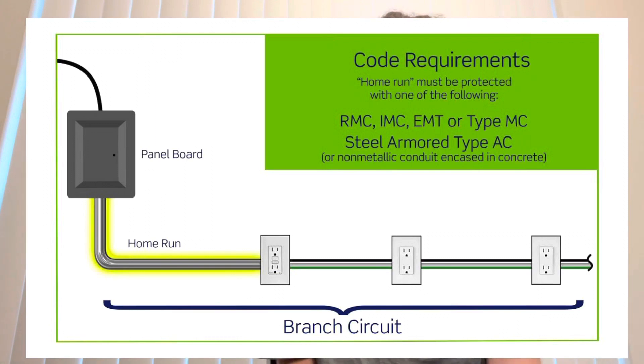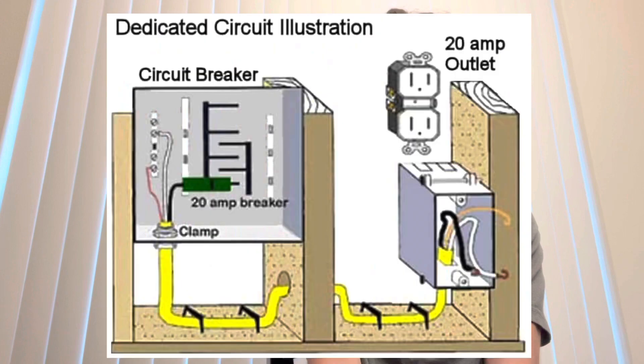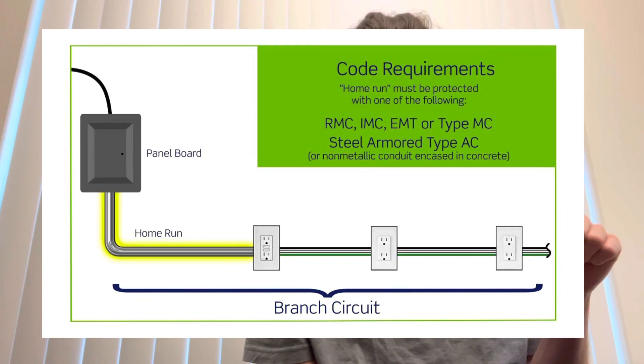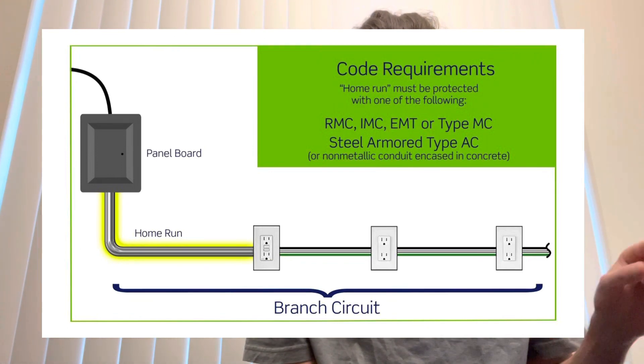Then you've got your home run, which is the beginning of a circuit back to the breaker in the panel box. That can be either an individual dedicated circuit — like your refrigerator or microwave — where it's just one wire going all the way back to the panel with nothing else on that circuit. Or in a kitchen you can have one home run that starts a circuit with multiple receptacles tied to it — three, four, five plugs on one home run.